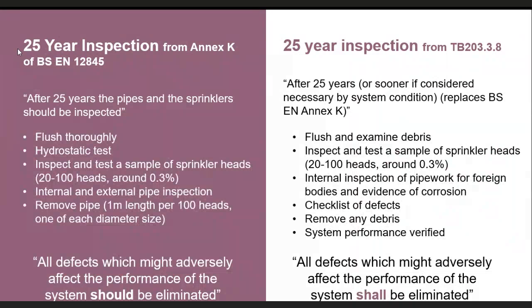And there's also a little statement which basically says we don't recommend doing that. I think the argument is if the sprinkler system has been sat at 6 bar for all of its working life, but then suddenly you put 15 bar of pressure into it, then you're going to get leaks. That doesn't actually show that there is anything wrong with it in the first place necessarily, but now you've got a whole load of problems to fix which you didn't have before. So that's a key difference.